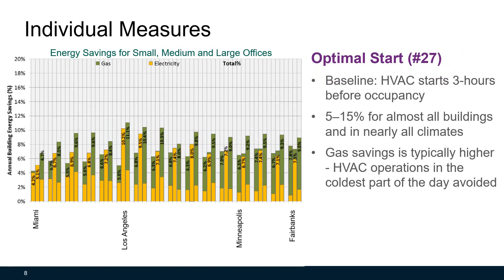The next measure is optimal start. The baseline for this strategy is that HVAC equipment starts three hours before occupancy. The optimal start strategy determines the optimal start time for HVAC equipment. 5 to 15 percent of energy savings can be achieved for almost all buildings and in nearly all climates, and gas savings is typically higher because HVAC operations in the coldest part of the day are avoided.